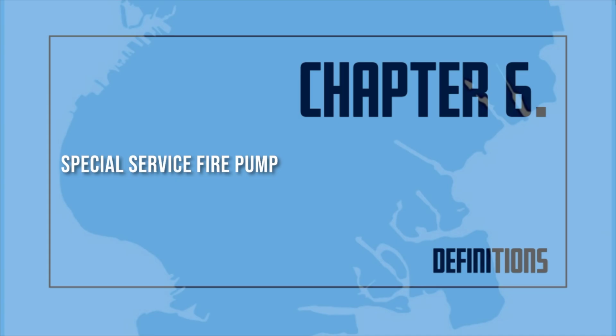Special service fire pump. A fire pump that is located above street level that receives its water supply from a gravity tank or suction tank supplying water to fire sprinkler/standpipe systems and/or fire department hose outlets. Special service pumps shall be maintained according to National Fire Protection Association 25 standard for fire pumps. Fold. A transverse bend or fold, occurring where the hose is lengthwise doubled over on itself, as on a pin rack.